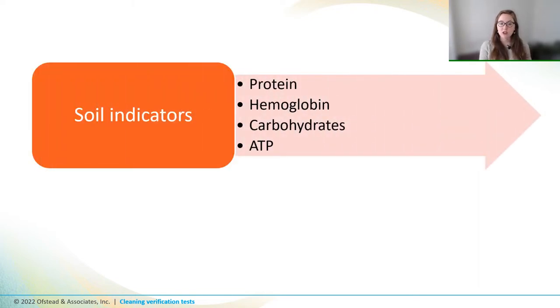When we think about biochemical tests that can determine if scopes are clean, there's really two buckets. First, there are tests that can determine if there's still soil by detecting protein, hemoglobin which is blood, carbohydrates, or ATP, or adenosine triphosphate, and this is a chemical that's released by living cells.